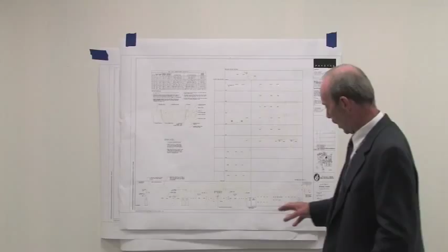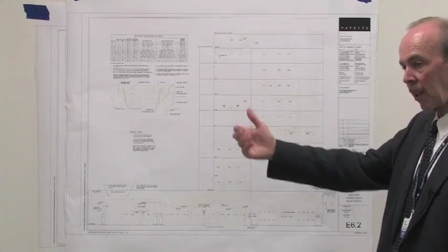So it's primary and secondary selectivity, just like you have in the main building, okay? Fully draw-out circuit breakers. We come off of these, come over to the south end of the building, rise up on the south side of the building with the conduit wire feeders. This building was not big enough to support a bus duct configuration, so we went pipe and wire.